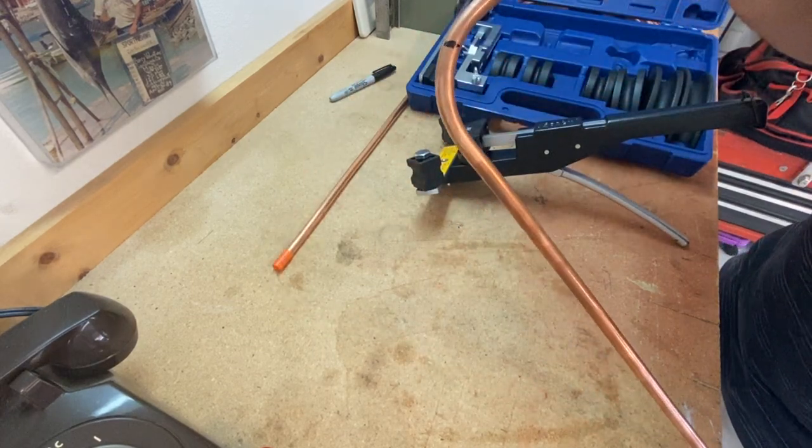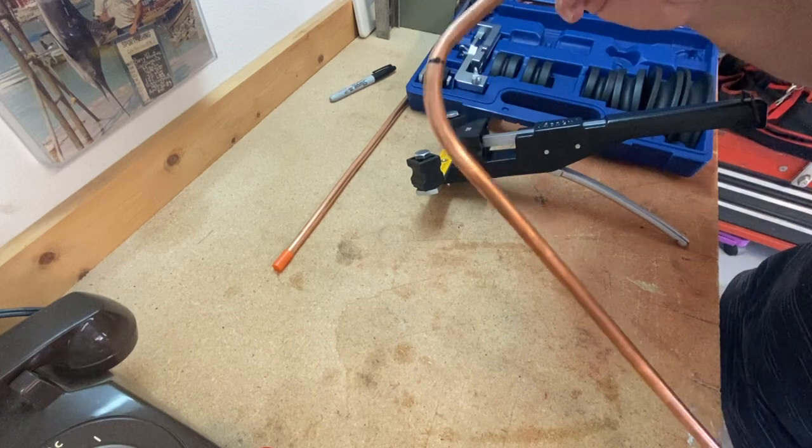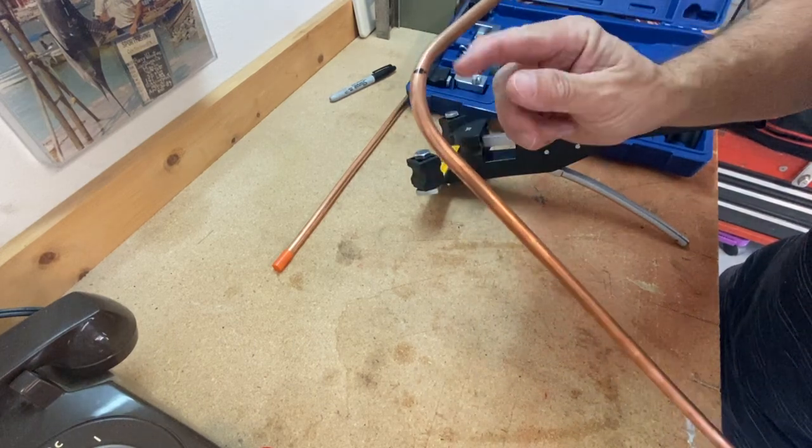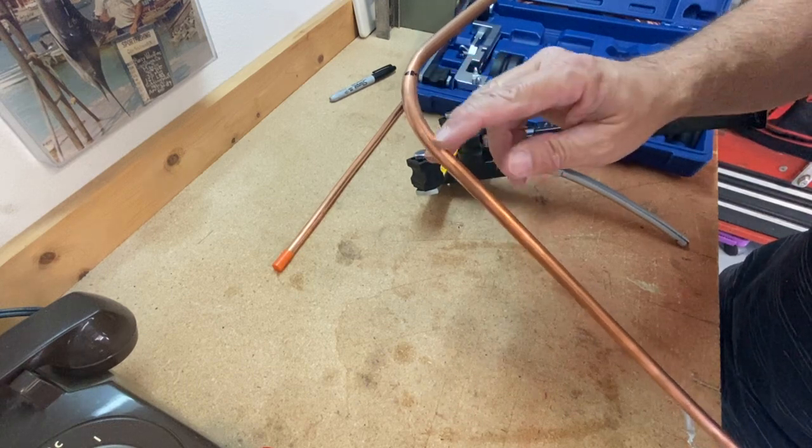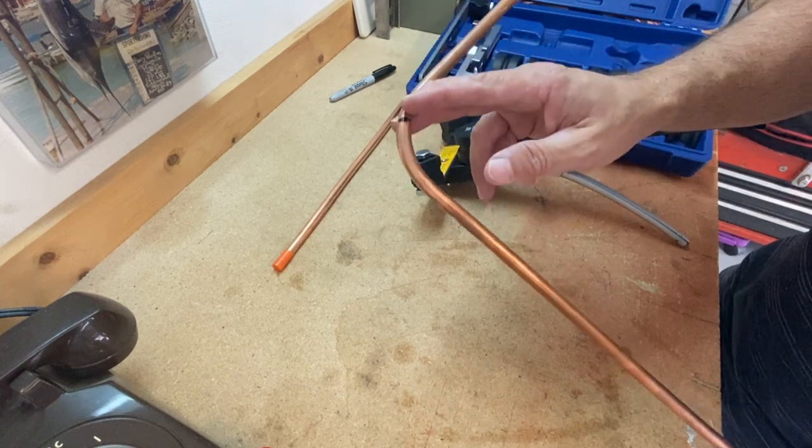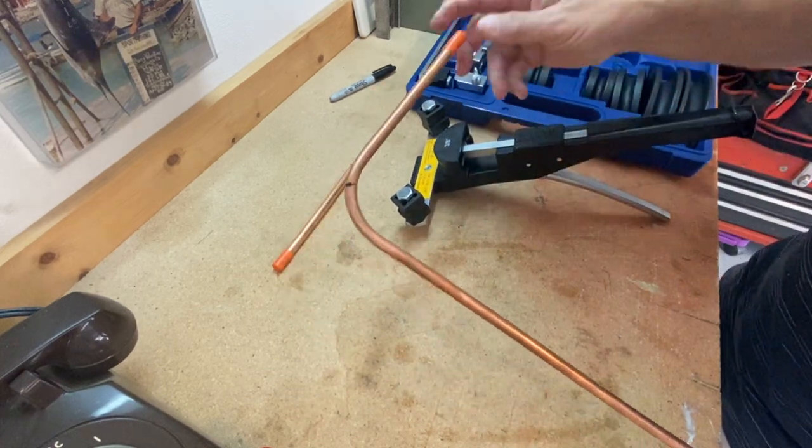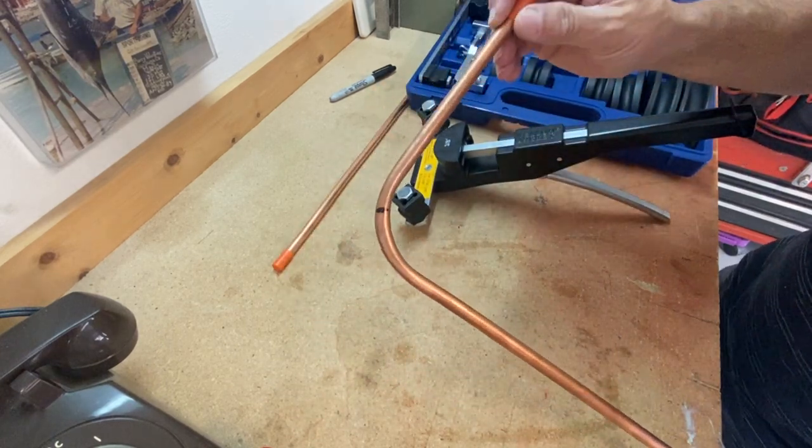Okay. And you can bend all the way up to seven-eighths tubing, makes a real nice full bend so that we don't crimp it. We don't put a crease in here where we would restrict any refrigerant flow. This tool is worth its weight in gold. It's just perfect tool for the use.